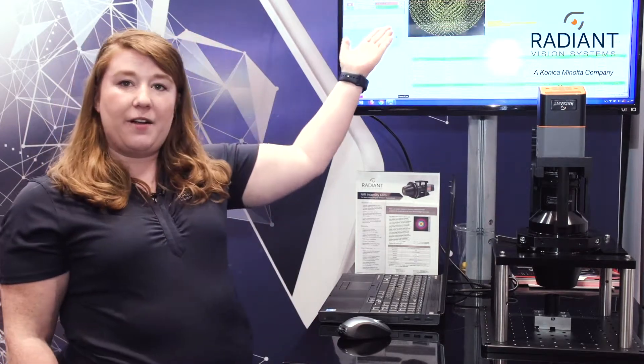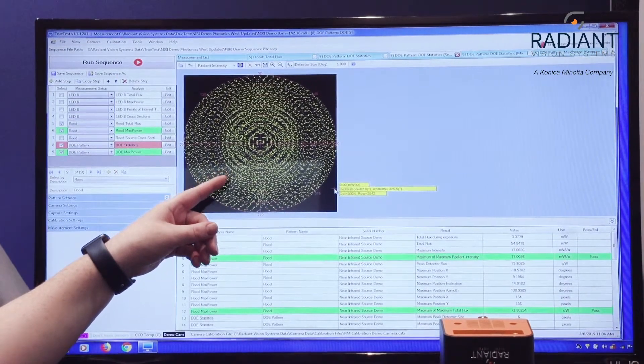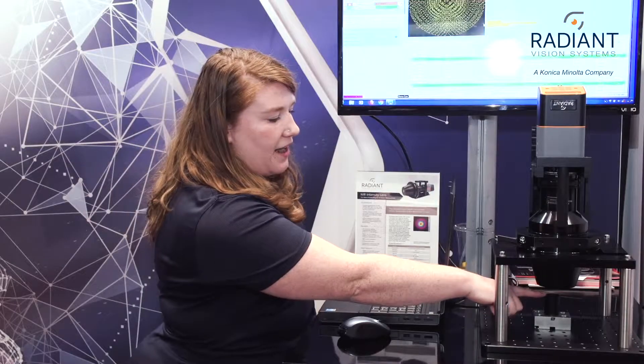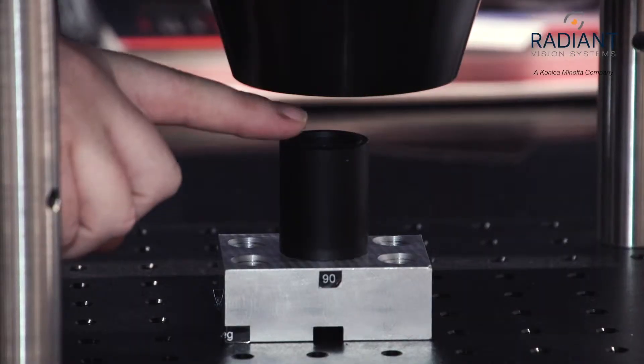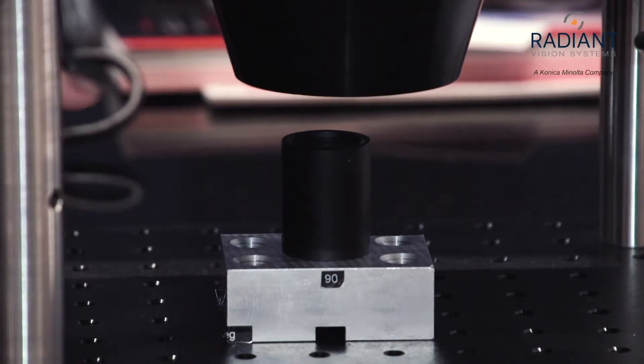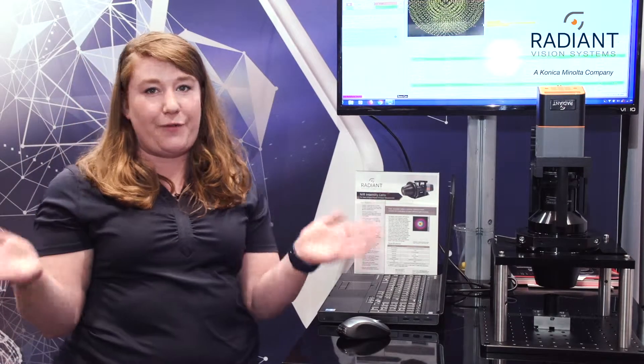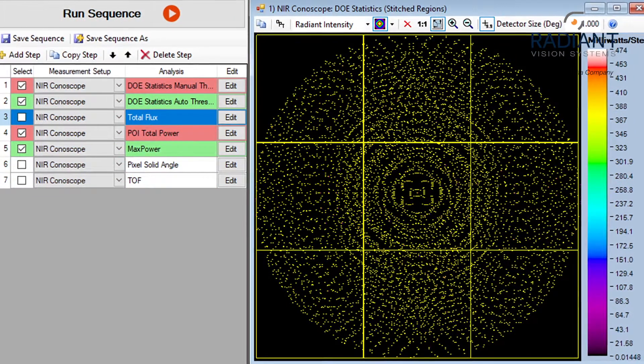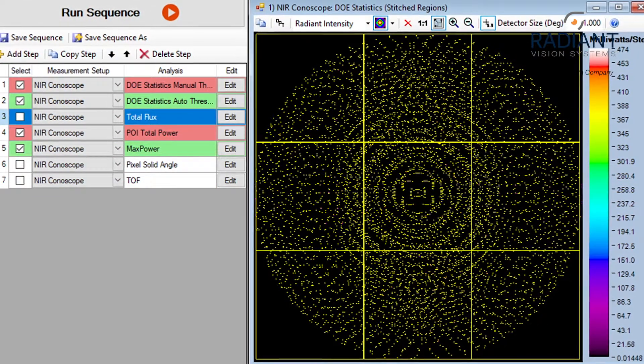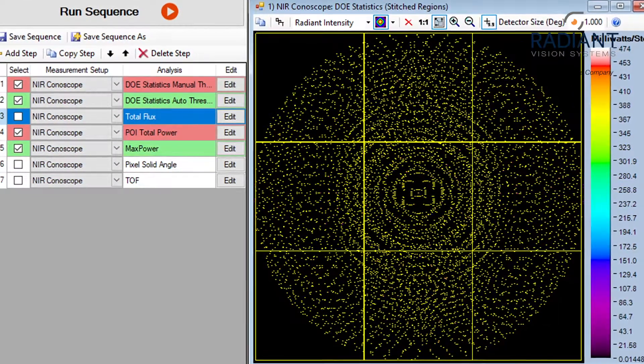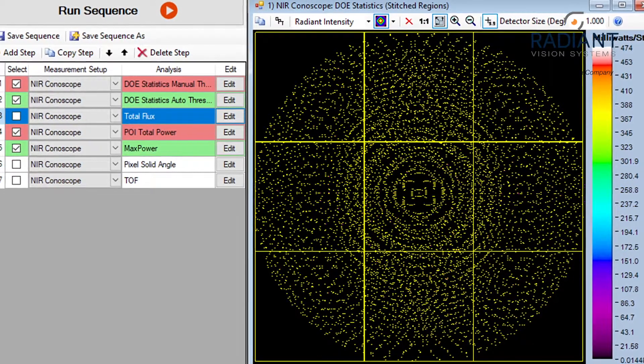When you have this type of device, what you care about is the output pattern as well as the radiant intensity. If you look up here we have some of the output from our device. You would put your DUT, device under test, down here. We would capture a full 140 degree field of view and output a pattern that looks like this, showing the radiant intensity of all of the thousands of DOE elements.